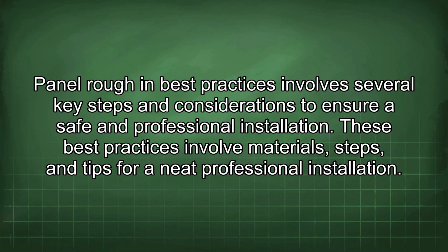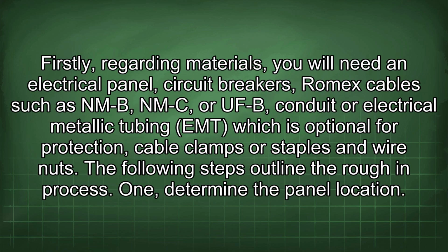Panel roughing best practices involve several key steps and considerations to ensure a safe and professional installation. These best practices involve materials, steps, and tips for neat professional installation. Firstly, regarding materials, you will need an electrical panel, circuit breakers, Romex cables such as NMB, NMC, or UFB, conduit or electrical metallic tubing (EMT), which is optional for protection, cable clamps or staples and wire nuts.